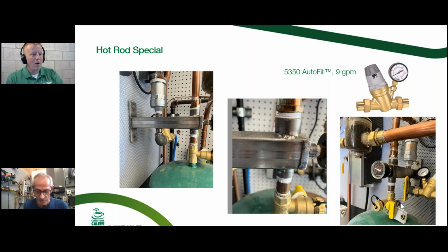Yeah, so if you are looking towards the future and you are looking for serviceability, you've got this little valve set up, and you can make this all out of separate components too, but the ability to drain off the water side is going to be ideal. I can't count how many jobs I would see with Extrol 60 tanks on these old gravity conversions where they just had a valve connected there, and if I knew then what I know now, I'm trying to bear hug this thing and unthread it. And meanwhile, I'm taking a bath and everything else. Make sure it's supported, make sure you can get the water out of it.